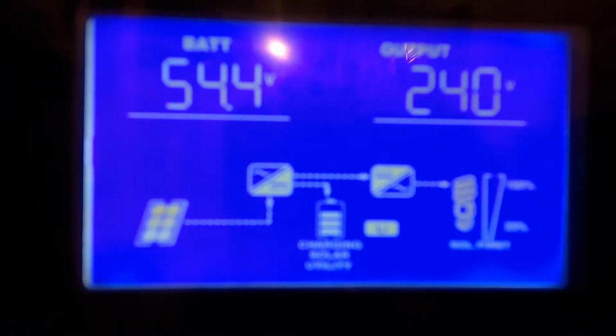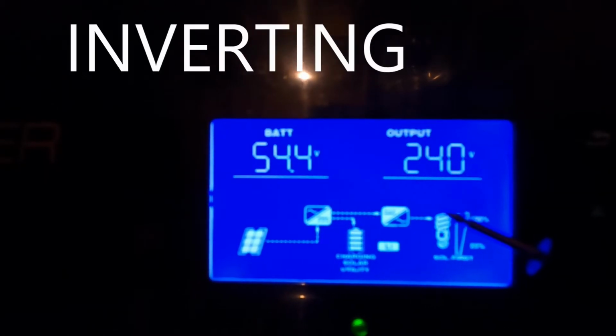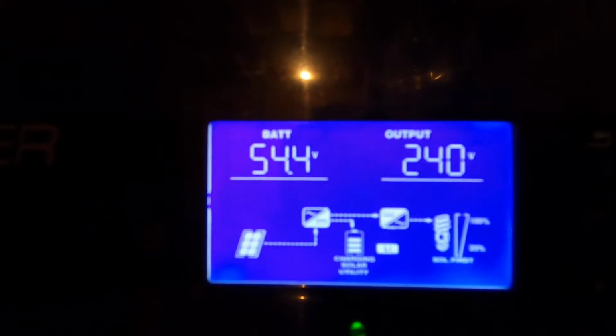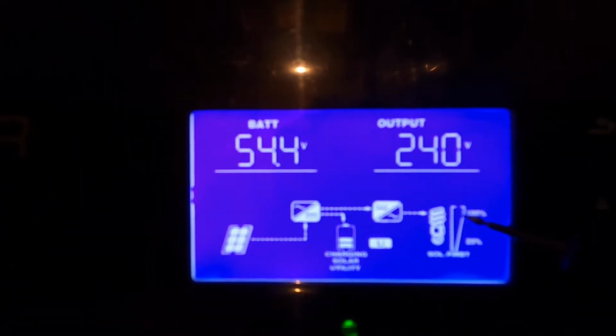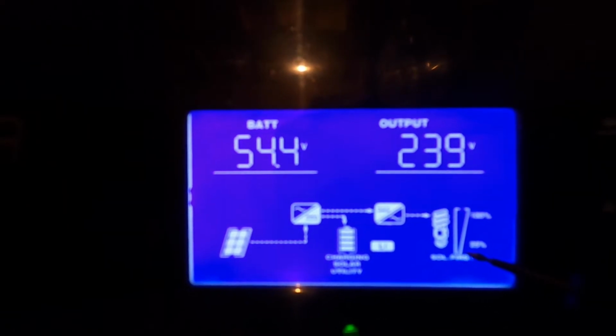And then the other arrow, that line is coming across, and that's indicating that the inverter, that's what this other box here, that symbol is for the inverter. And again, this thing doesn't want to focus properly. I don't know if that's better or not, but we'll try it. So lithium ion battery is charging, inverter is inverting, charge going out, power to the house, to the load, and this little bracket on this end over here shows the percentage of the load that's being used, and right now it's below 25%, very, very low. As they use more stuff, you'll see the little bars go up, similar to the battery concept for your percentage of load.